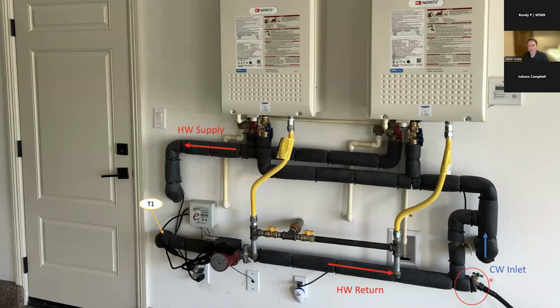So in other words, if the pump is running and 5 minutes goes by and it's not seeing that rise in temperature or that temperature lockout, then the pump is just going to automatically turn off. Because usually what that means is if the pump is running for 5 minutes and it doesn't see any change in temperature, it usually means that there's air trapped in the line. So the pump might be spinning, but it's not actually moving any hot water. And when that happens, the pump will overheat because it needs to have that fluid traveling through it. It'll overheat and it'll just die, and then you need to replace the pump. So we have that automatic timed lockout to prevent that airlock from damaging the pump.